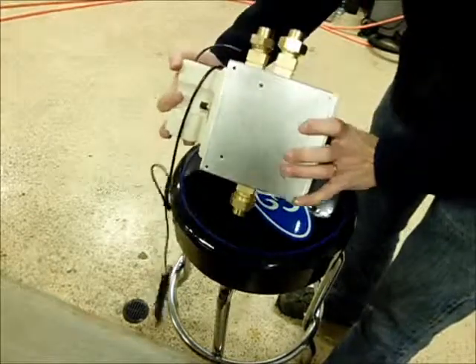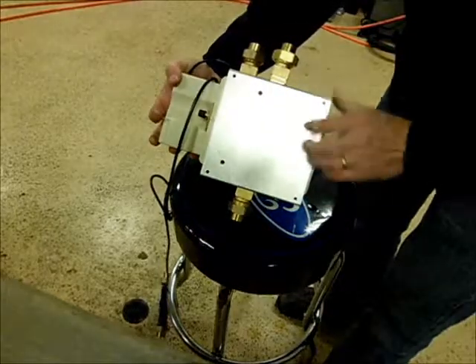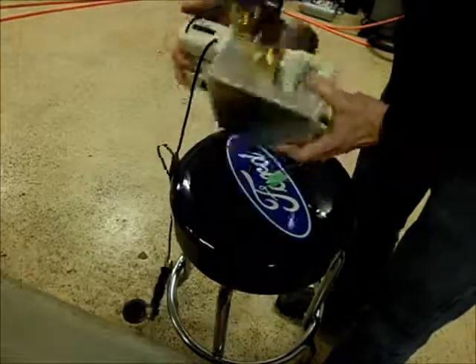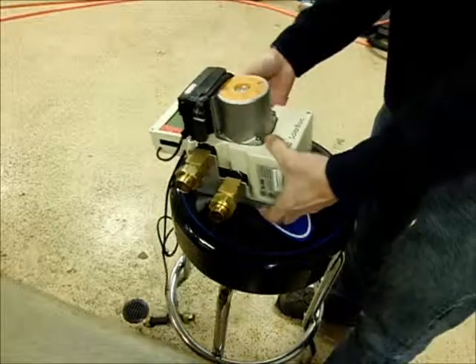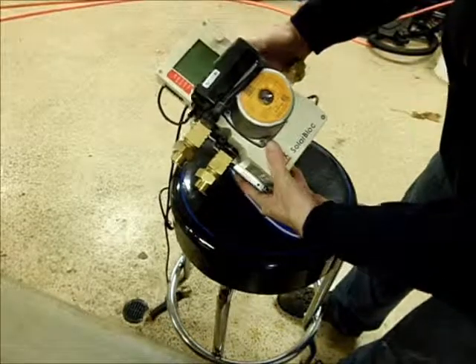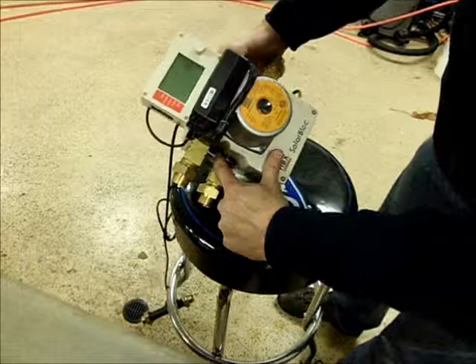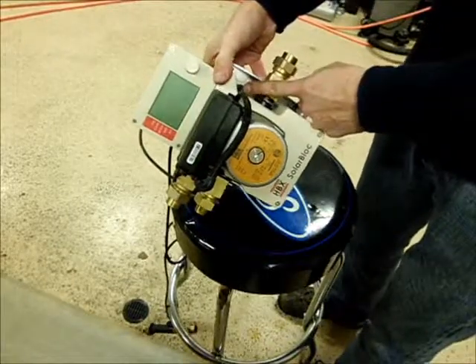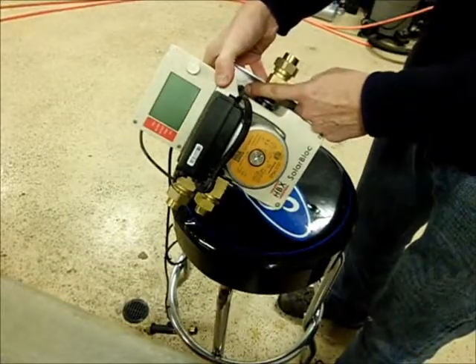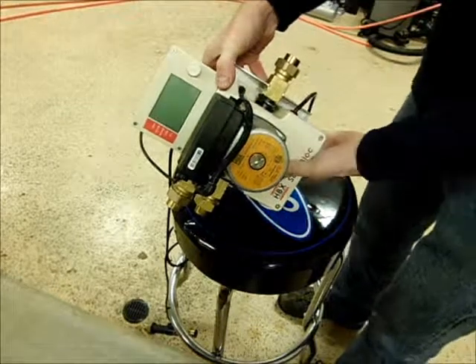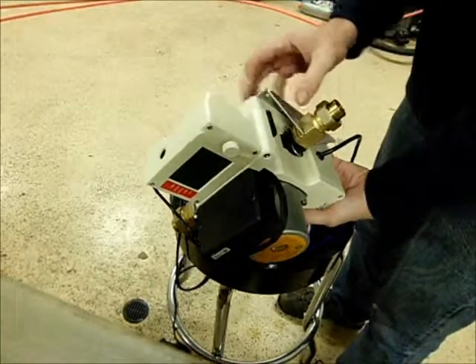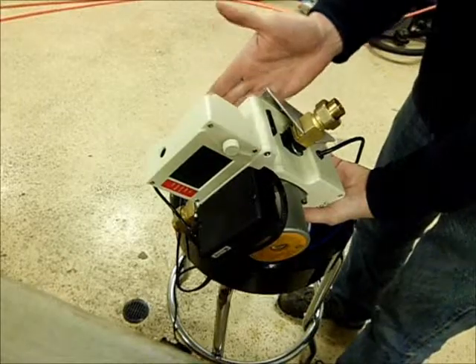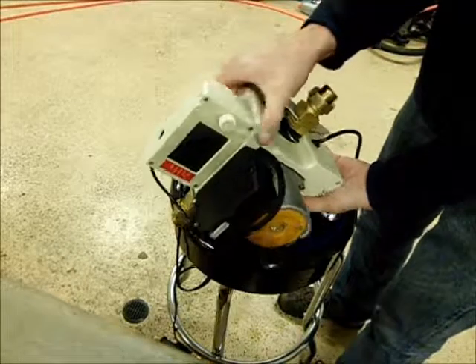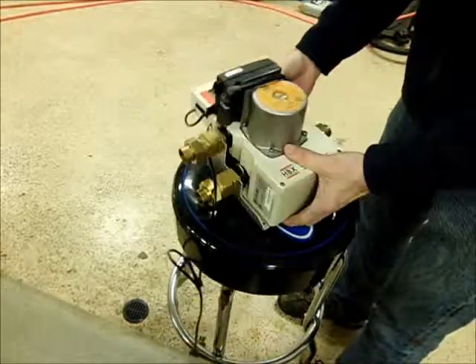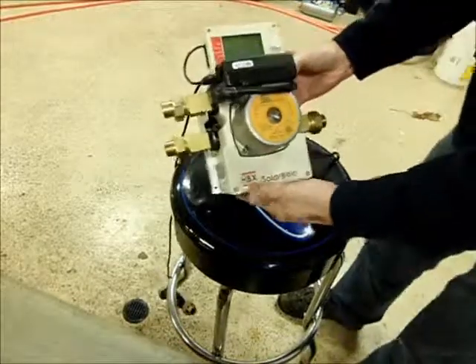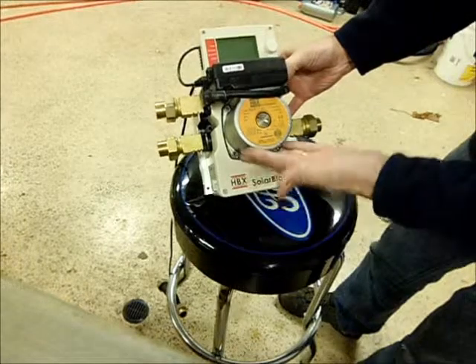Now on the back side, the 2 mounting holes line up fairly well. And when you're mounting this, you can use deck screws or whatever, but if you're using deck screws, you want to put a washer on there, because that is a flat head right there, and it's also a flat head right here. Ideally, if you're using a machine head flat type screw that's at least 2.5–3 inches long, you're going to have some plywood that you mount on your drywall, and this will screw right to your wall, and you can make all your plumbing connections from there. So that's the new HBX Solarbloc with the bigger pump.